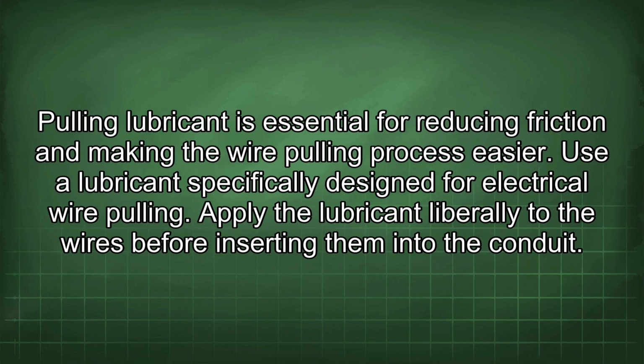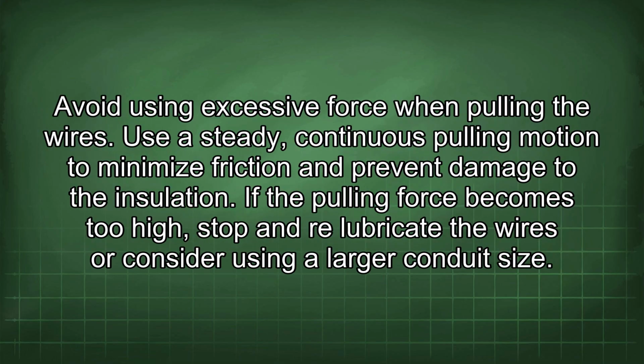Pulling lubricant is essential for reducing friction and making the wire pulling process easier. Use a lubricant specifically designed for electrical wire pulling. Apply the lubricant liberally to the wires before inserting them into the conduit. Avoid using excessive force when pulling the wires. Use a steady, continuous pulling motion to minimize friction and prevent damage to the insulation. If the pulling force becomes too high, stop and relubricate the wires or consider using a larger conduit size.